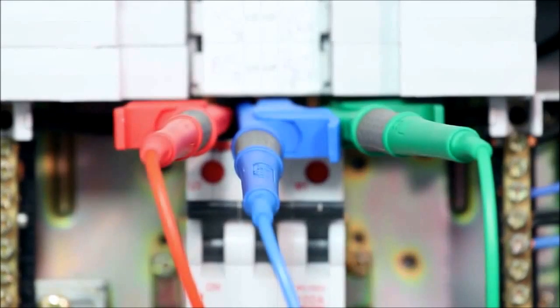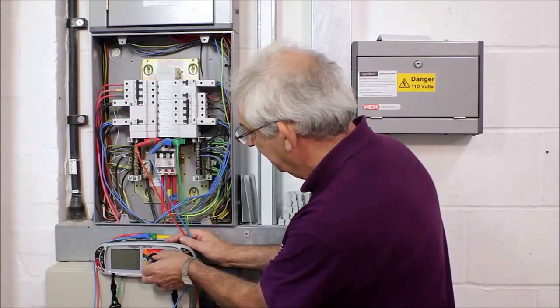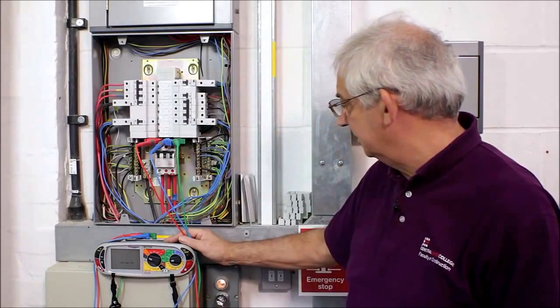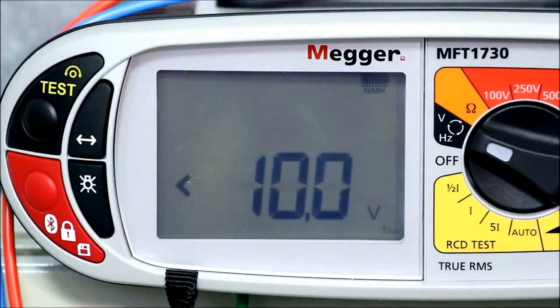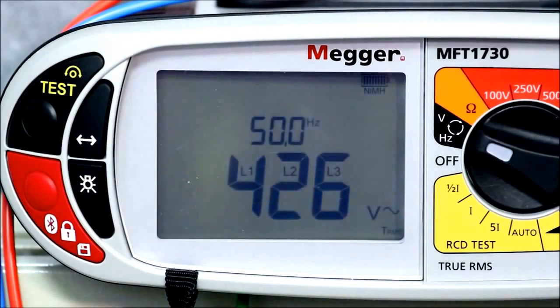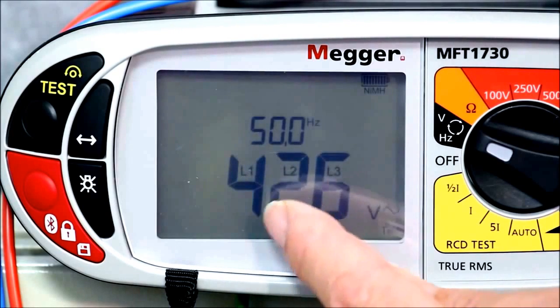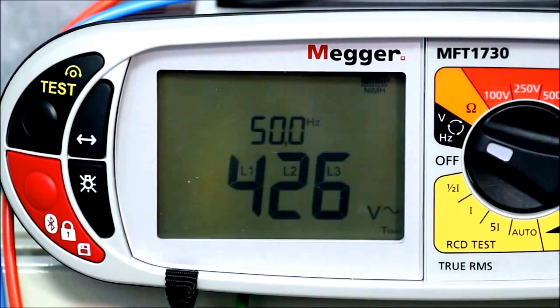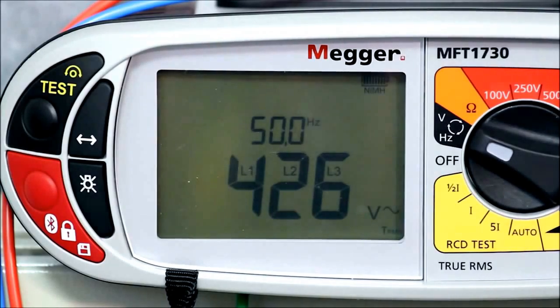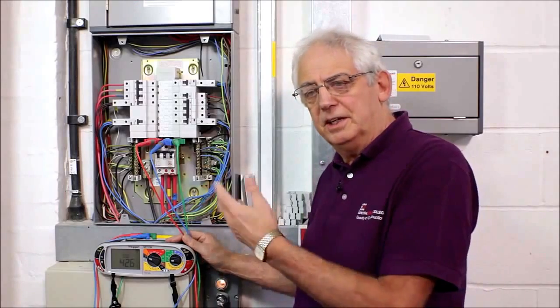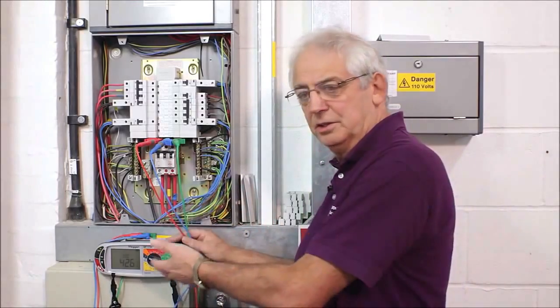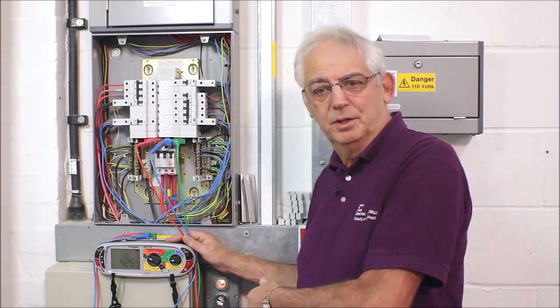Just connect our leads up onto the 3 phases or 3 lines, turn it on to phase rotation, and we should, with any luck, see it comes up and it says L1, L2 and L3, which shows quite clearly that the phase rotation is the right way around. If I connect it a different way around, we can see what the problems would be, or how it would show you that it's the wrong way around.